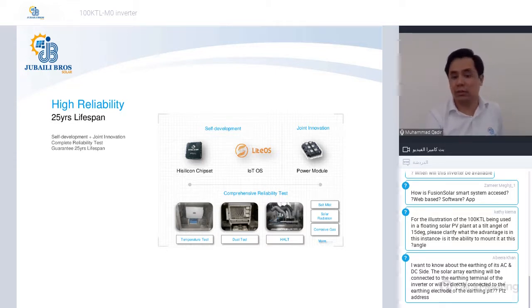And Huawei does a high acceleration life test of the inverter, which is actually exposing the inverter to sub-zero temperature of around minus 40 degrees Celsius and increasing the temperature to almost 90 degrees Celsius in order to make sure the operation of the inverter is still successful. Yet in the data sheet, you will find that the inverter is specified to operate from minus 25 to 60 degrees Celsius. And also during the test, the switching of the inverter is constantly happening to make sure that there is no failure of any component.